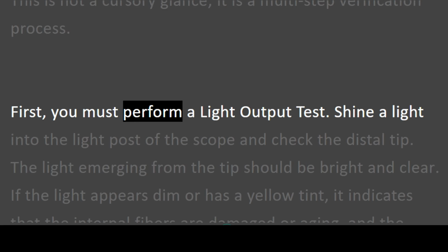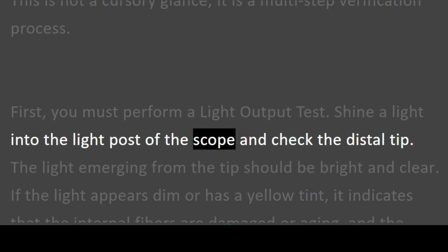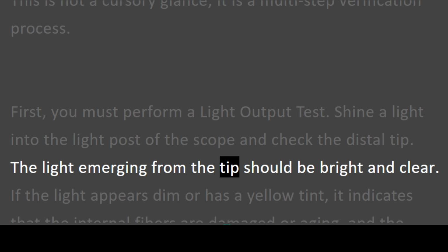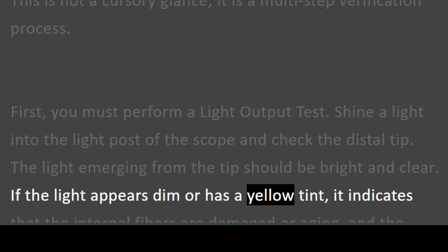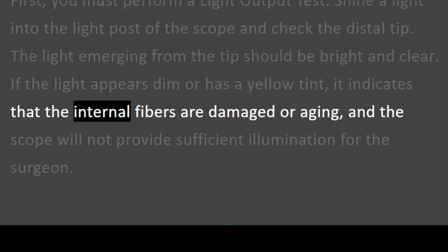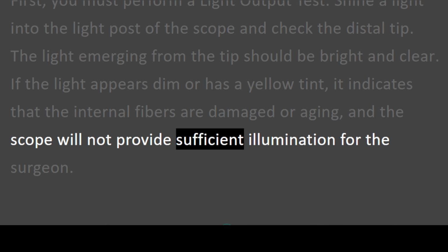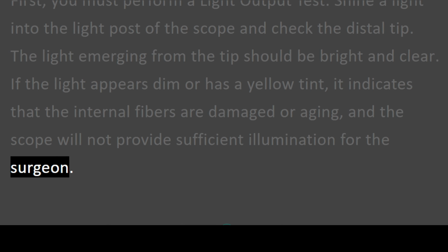First, you must perform a light output test. Shine a light into the light post of the scope and check the distal tip. The light emerging from the tip should be bright and clear. If the light appears dim or has a yellow tint, it indicates that the internal fibers are damaged or aging, and the scope will not provide sufficient illumination for the surgeon.